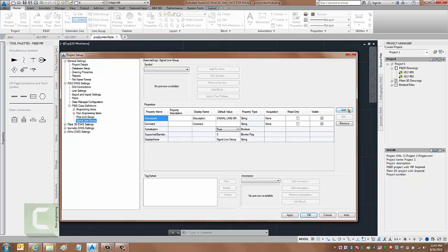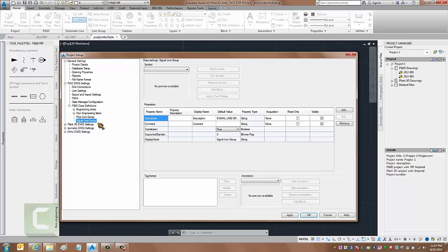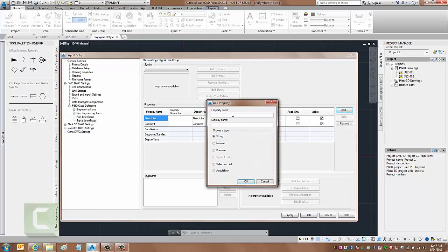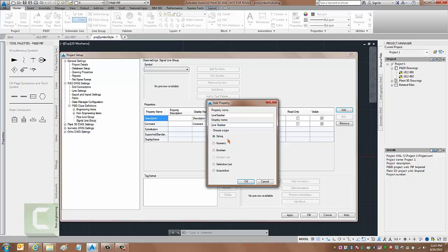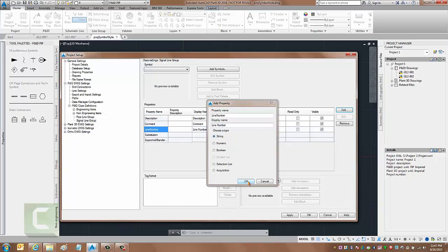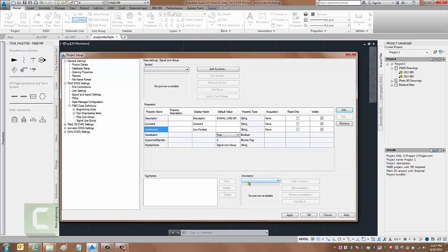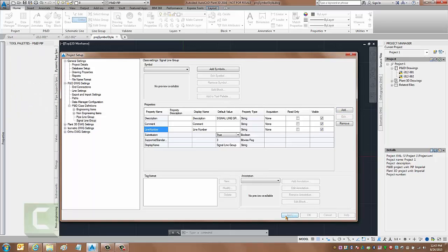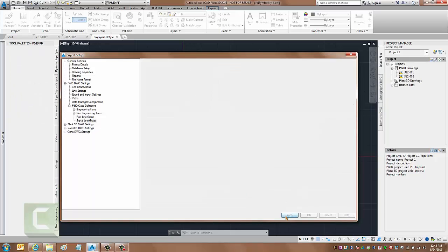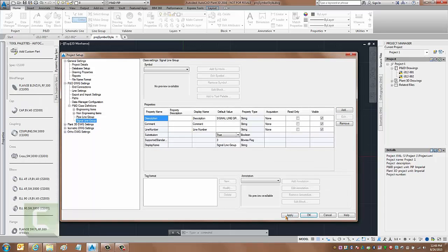So I'm going to come over here to the add button while I'm on the signal line group. Under here, I'm just going to add line number. I like to put a space between the display name. That's just a string, if you look back on the pipeline group, line number is just a string. Hit OK, and that adds the line number in there. Now my habit is to hit apply after I've done a change like that so it gets remembered, because now I have to go over here to the engineering items.